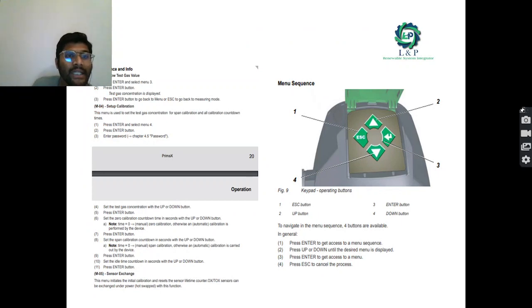Next, if you want to see the test gas value, you go into menu 3. For that, press the enter button, select menu 3, and press the enter button. The test gas concentration will be displayed. And if you want to do the calibration, you go inside the M04 menu. Press the enter button, select menu 4, and press enter. Then give the password; the default password will be 0000.